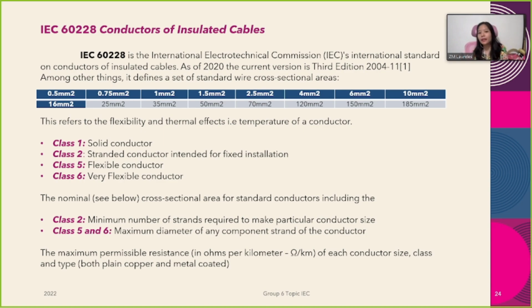So, meron tayong apat na class, which is class 1 solid conductor, class 2 stranded conductor intended for fixed installation, class 5 flexible conductor, and then yung class 6, which is a very flexible conductor. The nominal cross-sectional area for standard conductors, including the class 2 minimum number of strands required to make particular conductor size, and then class 5 and 6, yung maximum diameter of any component strand of the conductor. So the maximum permissible resistance of each conductor size, class, and type.